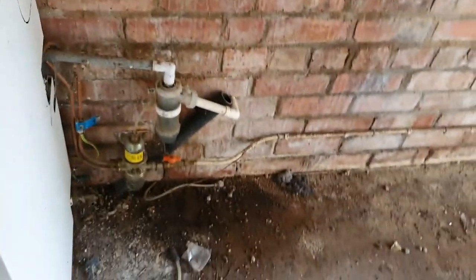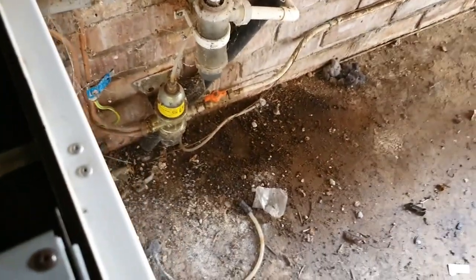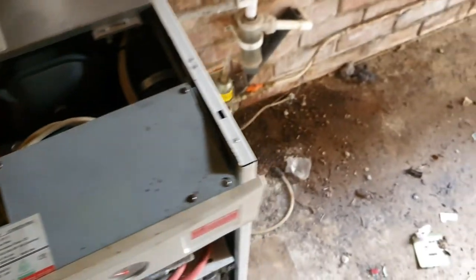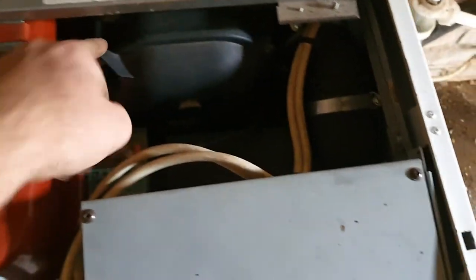This is one of the first Worcester Heatslaves they brought out - this is the one with the external condense trap. It's got their downward-firing burner; I think it's a Riello burner on these. I'll check the expansion vessel pressure as well, take the baffles out, clean the secondary heat exchanger. It's just six screws on top and then the fins just pull out. The flue has got a bracket at the top - it's not screwed at the bottom so we can pop a screw in there.